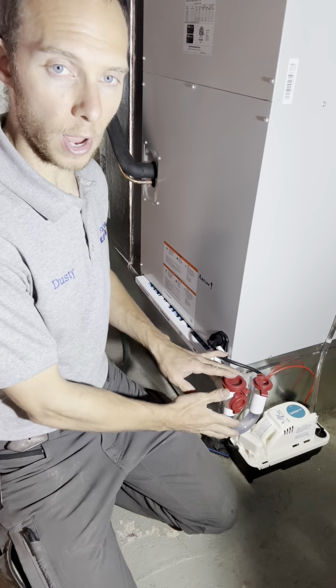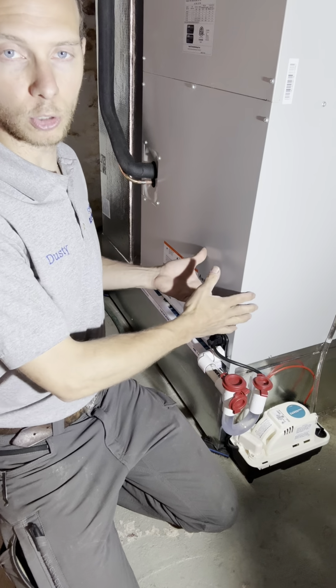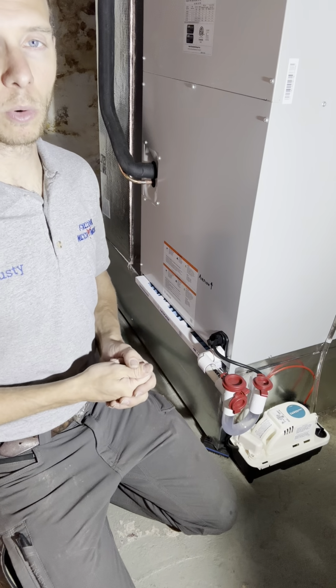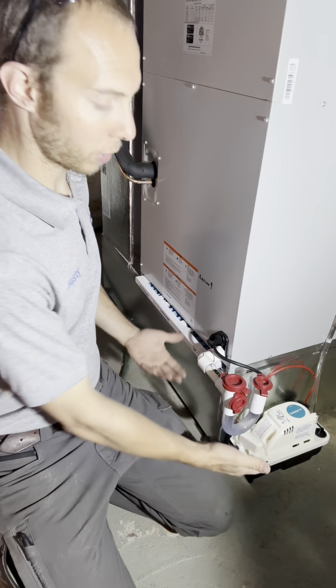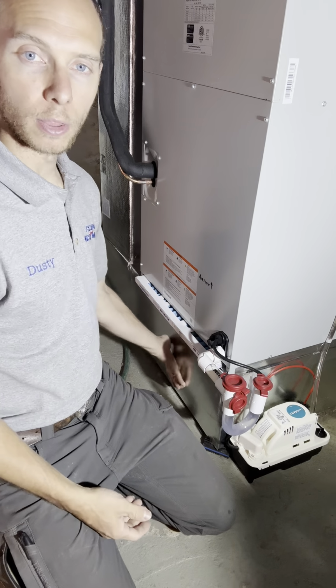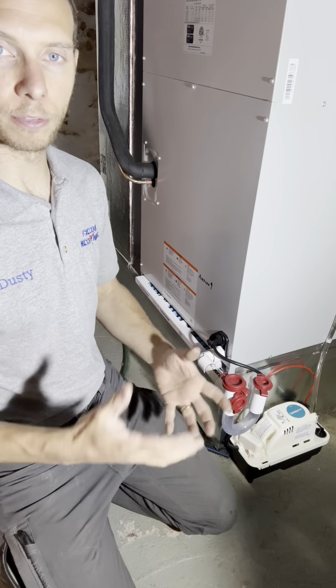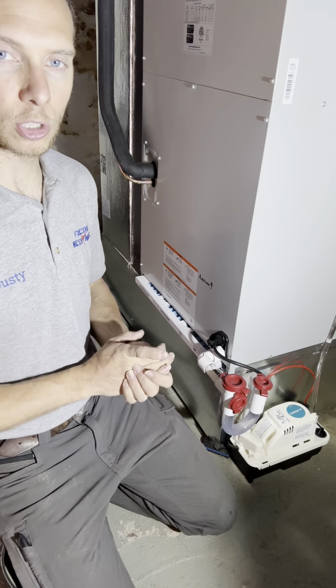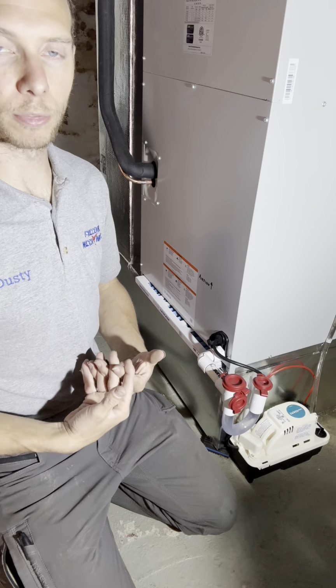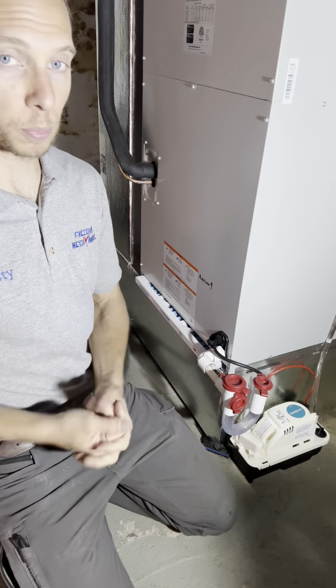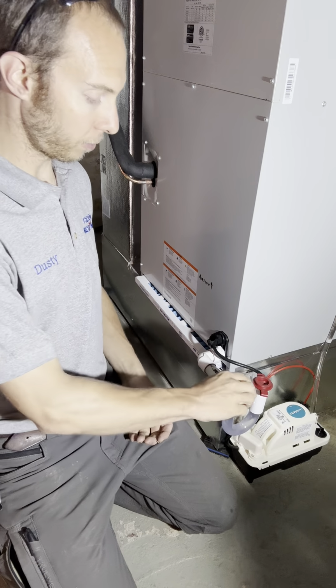So if this is dry, it might hold water in the unit, and if it runs a long cycle on that first cycle, it can overflow and run down into the bottom return box of the air handler. So we want to pay attention to that when you go to start it up for the first time in the spring or summer. Just flip the cap open here.